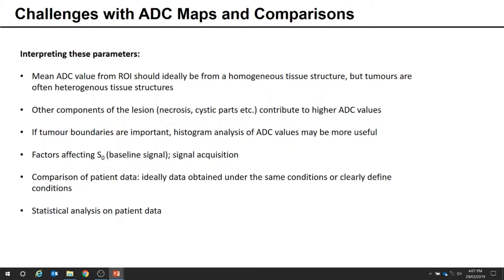There are also other factors affecting the baseline signal before the diffusion gradient pulses are even applied. The literature shows significant differences in ADC values between different scanners, gradient systems, RF coils, and even the software or algorithms used to calculate the ADC. One way of dealing with this is to determine ADC thresholds that are site-specific, or clearly state the conditions and limitations of a certain setup, or correct for differences between scanners and setups.